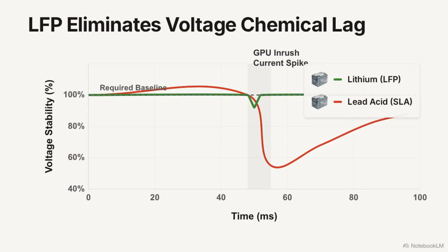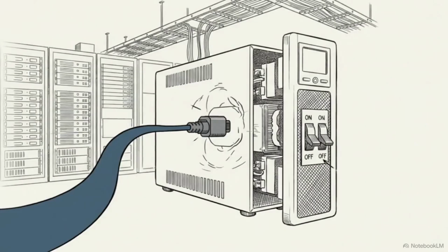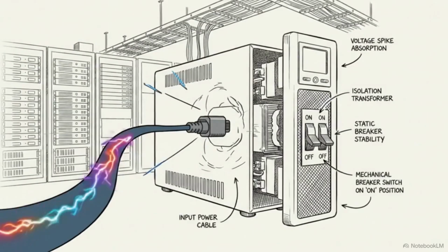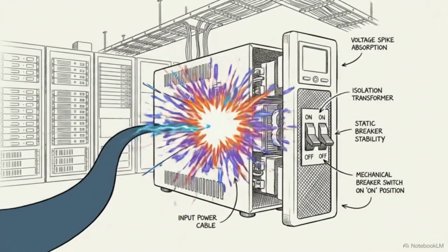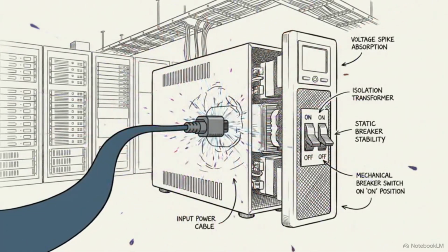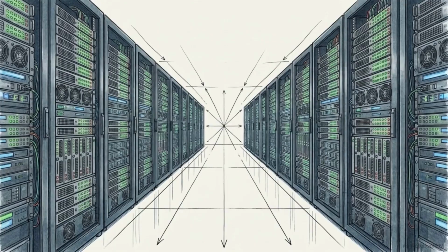It provides the superior ride-through needed to sustain power during these high-density demands. Because LFP supports these violent spikes without dropping voltage, it prevents the UPS from tripping its own safety breakers. This shift synchronizes your power delivery with the physics of modern high-performance computing.